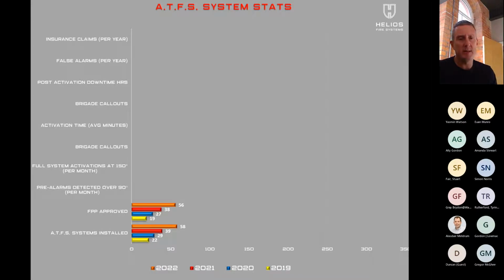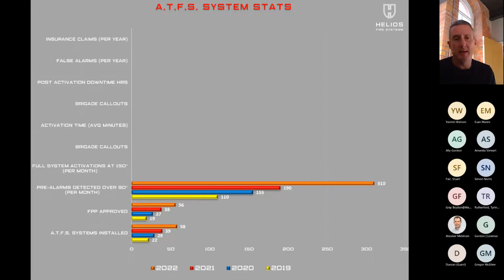Going into how the system detects, we have 2 levels of detection warnings on the system, so we don't actually have a fire breakout. Our first alarm warning is a pre-alarm set at 90 degrees, so any temperature within a waste pile, bale pile, or anywhere inside that building that hits 90 degrees at 50 millimeters square, we get a pre-alarm, which warns us prior to any fire breakout or thermal runaway. Going back from the bottom, in 2019 it was 110, and today we're at 310 pre-alarm activations per month.